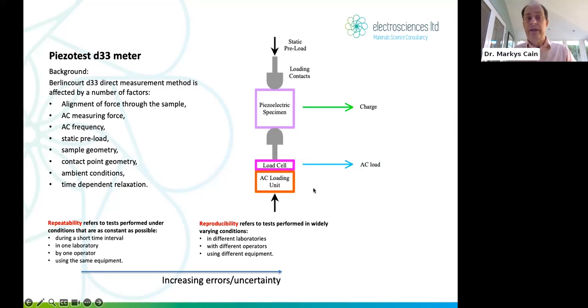Now, the piezo test meter, the Berlincourt system, doesn't quite work like this. What you have is an AC loading system. We don't really have a load cell though. Sometimes they do actually, some of them do have load cells. The newest ones do, but the way it works is a bit different. They have another sample underneath this piezoelectric specimen, which is a piezoceramic material of known calibrated piezo response.